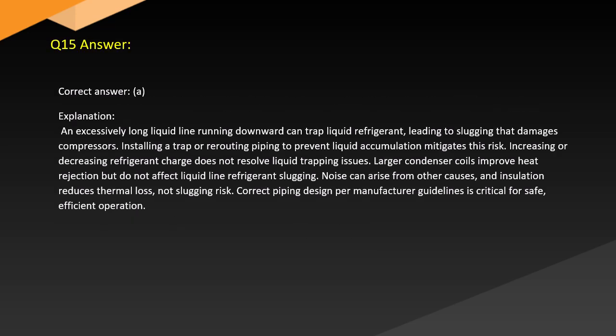Answer. Correct answer: A. Explanation. An excessively long liquid line running downward can trap liquid refrigerant, leading to slugging that damages compressors. Installing a trap or rerouting piping to prevent liquid accumulation mitigates this risk. Increasing or decreasing refrigerant charge does not resolve liquid trapping issues.